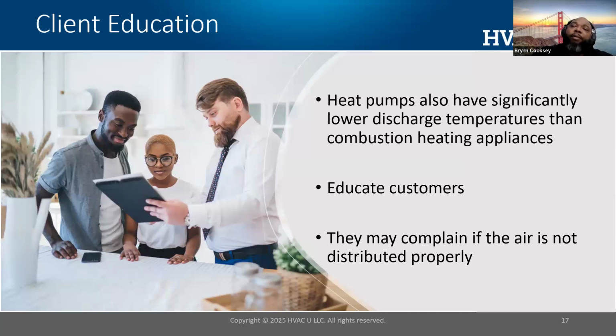Now, if you're working in a program and you're working with clients, you have to provide some type of education. With heat pumps, the way they operate, when I'm working with a furnace, I'm burning a fuel and I have really hot exhaust gases that exchange their energy with the circulating air. So from a furnace standpoint, the air coming out of the registers is significantly warmer than it would be for a heat pump, which is simply moving heat from one place to another. So, prior to working with a customer that is going to utilize a heat pump, you have to prepare them for the differences that they're going to encounter.